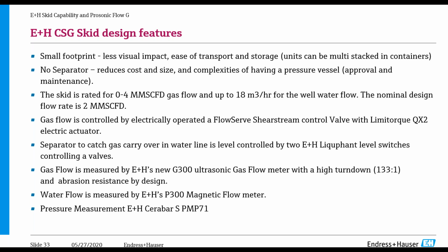The G300 is also a full bore flow meter. Typically we see quite low pressures coming from the well, and using an orifice plate, for example, creates a huge pressure drop. So we're really starting with very low pressures, and to put an obstacle in the flow path that's going to create a massive pressure drop is normally not beneficial. So it's a full bore flow meter with very minimal or negligible pressure drop across the flow meter itself.